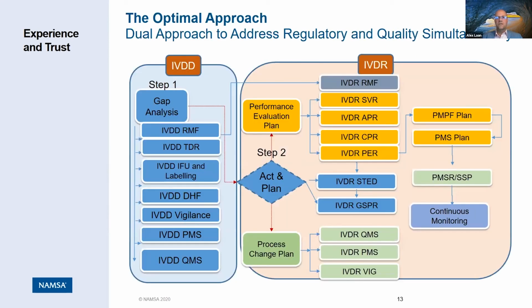My final slide for today: optimal approach. In case you are still under the IVD directive and you want to move over to the IVDR, the best way is to do a gap analysis and take a look at what you currently have. What do you have in your risk management file? What do you have in your technical dossier? Instructions for use, labeling, DHF, and determine what the gaps are.